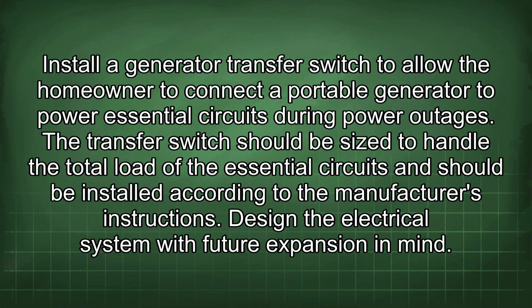Install a generator transfer switch to allow the homeowner to connect a portable generator to power essential circuits during power outages. The transfer switch should be sized to handle the total load of the essential circuits and should be installed according to the manufacturer's instructions.